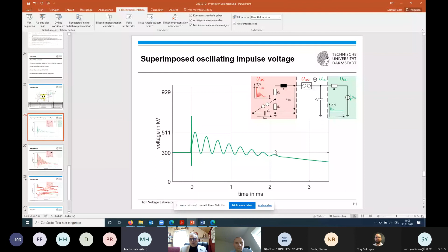Now imagine one slide further, you do not have the device under test connected to the generator. Then you just have the assembly and no capacitance. You have just a small earth stray capacitance, which will be fed with this impulse. And there you get a very high and very steep voltage, which is generated on the one electrode of the spark gap. This voltage overshoot naturally triggers the spark gap without any trigger mechanism. This works for OLI quite well. When you would like to make such tests with conventional voltage shapes, then you need a trigger mechanism, yes.